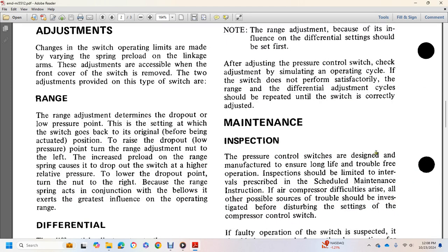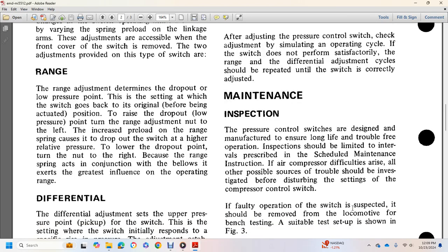Maintenance inspection: the pressure control switch is designed and manufactured to ensure long life and trouble-free operation. Inspection should be limited to the intervals prescribed in the scheduled maintenance instruction. If air compressor difficulties arise, all of the other possible sources of trouble should be investigated before disturbing settings on the pressure control switch.